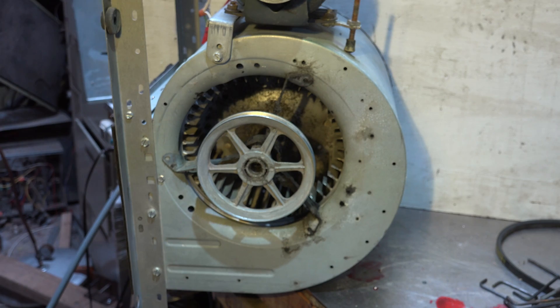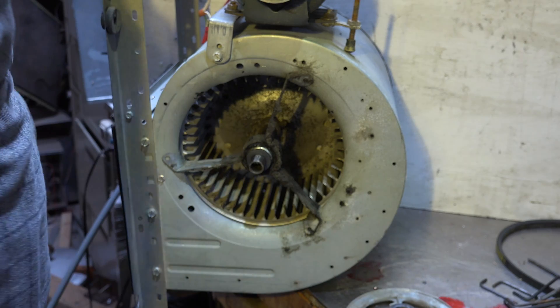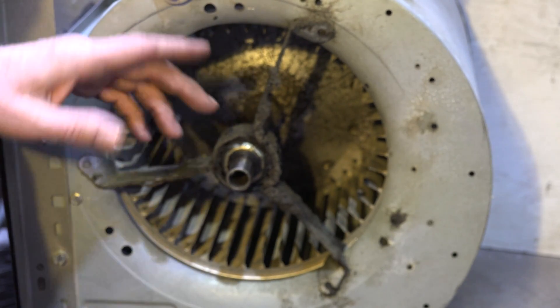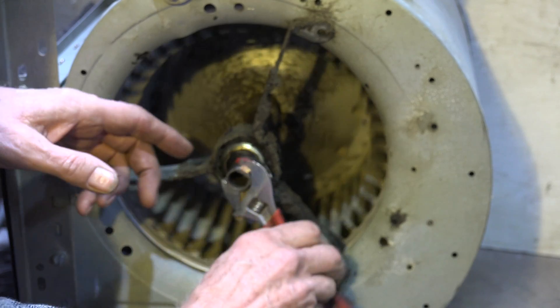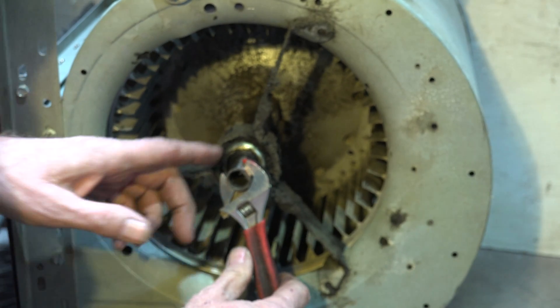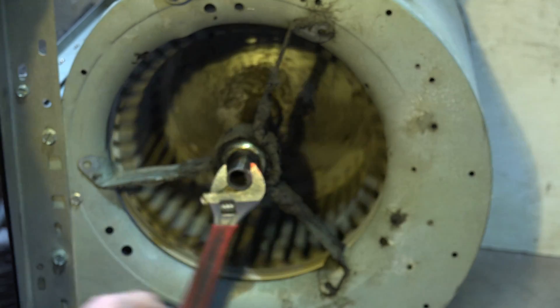Okay, so what was wrong with the blower? Got the belt off. Looking close at this, you can see this is not a ball bearing — this is a bushing, a bronze bushing, right down there. This whole assembly here is rotating, and it actually rotates pretty smooth. That's a rubber sleeve right up there, and it's riding on that rubber sleeve right now.